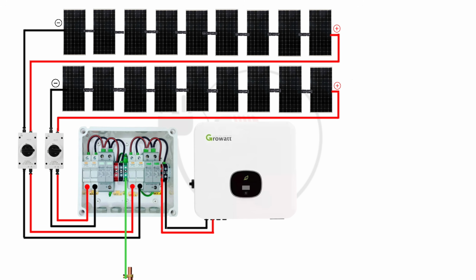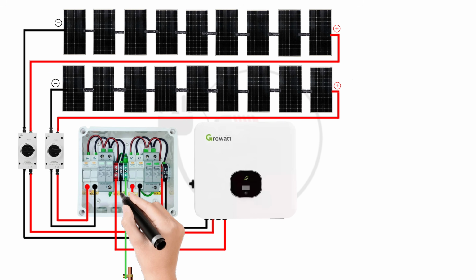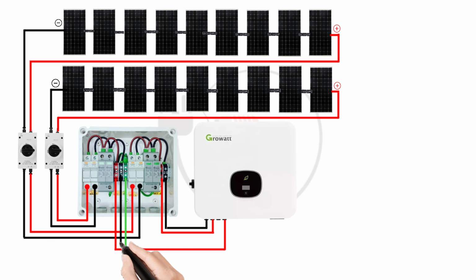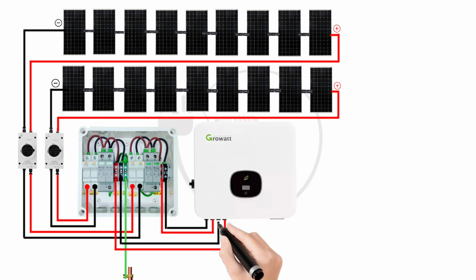Again, repeat the same connections. Connect the positive output of the MCB to the positive PV input of the solar inverter. Connect the negative output of the MCB to the negative PV input of the solar inverter. Important considerations. DC systems are polarity sensitive. It's crucial to match the polarity correctly. Reverse polarity can damage equipment. Always double check all the connections.